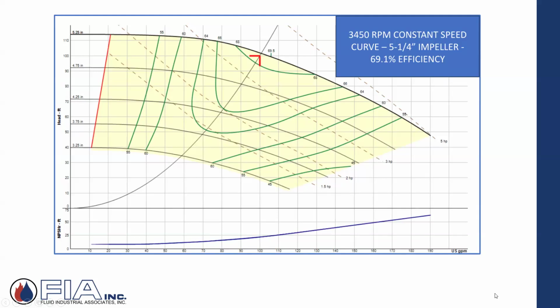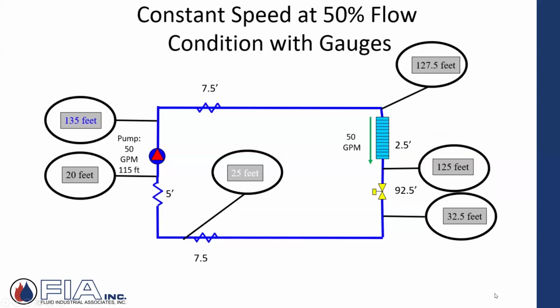As I start backing up on the curve, down here in the middle, where I'm trying to circle with this arrow, it says 50 GPM. So 50 GPM is where it intersects that pump impeller curve, which is where it has to operate. The pump has to operate on that curve. It's developing about 115 feet of head. That's all we're stating here: when it's full flow, it's 100 gallons a minute, 100 feet of head. I back up, valves close, I'm at 50% of flow, and I develop a higher head, 115 feet. Same phenomenon is taking place. Look at this pressure drop across what this control valve has to absorb, 92 feet.